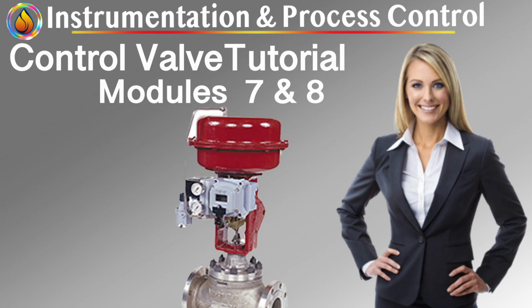Impact on loop stability. Valves are not neutral participants in control loops. They shape loop dynamics continuously. Interaction with controller tuning: controller tuning assumes predictable gain, minimal deadband, and consistent response time. Valve imperfections violate all three. Consequences: overtuned loops oscillate, undertuned loops drift and lag, and retuning treats symptoms, not causes. No tuning method can compensate for poor valve dynamics indefinitely.